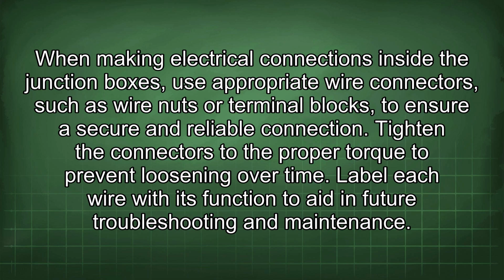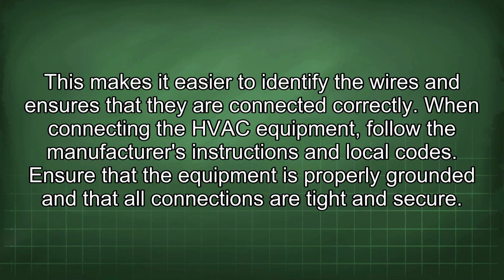When making electrical connections inside the junction boxes, use appropriate wire connectors such as wire nuts or terminal blocks to ensure a secure and reliable connection. Tighten the connectors to the proper torque to prevent loosening over time. Label each wire with its function to aid in future troubleshooting and maintenance. This makes it easier to identify the wires and ensures that they are connected correctly.